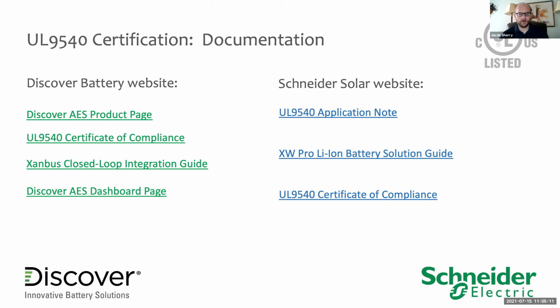I could take that one — I believe they're referring to our MPPT disconnect RS solution. I don't know that there's a minimum PV input voltage limitation required to detect the arcing. On the battery side, I know it's down to about 22 volts, so it'll even work with 24 volt systems. It also supports our lower voltage controllers, which can operate up to 150 volt maximum input. I don't think there's any limitation in terms of detecting low voltage arcs, so that should not be a problem, as long as you're within the operating range of the MPPT controller.